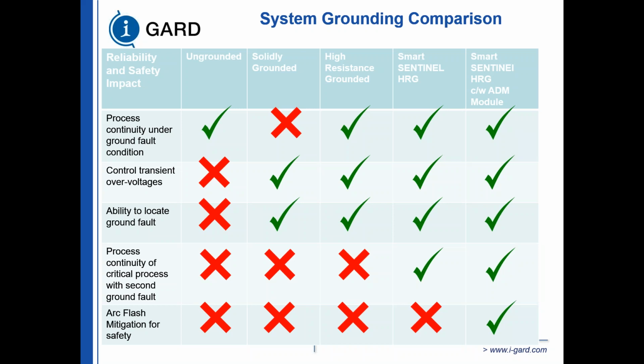High resistance grounded systems, you're going to get the process continuity, and this is a standard HRG system, and we make those as well. You're going to control transient overvoltages, because the transient overvoltage is basically going to be at 173% of the line to neutral voltage. Ability to locate the ground fault? Yes, we can do that because the ground fault is going to have pulsing, and we can locate where the fault is.